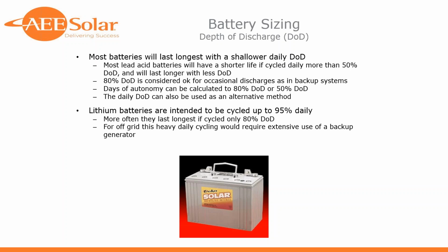Now, for an off-grid system, 2 or 3 days of autonomy, you're not really cycling that battery more than 20 or 30% per day, and they should last a pretty good long time, depending on which type. So you are looking at balancing the depth of discharge with the cost of the battery. Now, for a backup system, your number of cycles is generally fairly small. You're only looking at a dozen cycles per year probably. And so even with a lead battery, an 80% depth of discharge is really not out of line at all for backup systems, and that's generally what's used for that capacity.